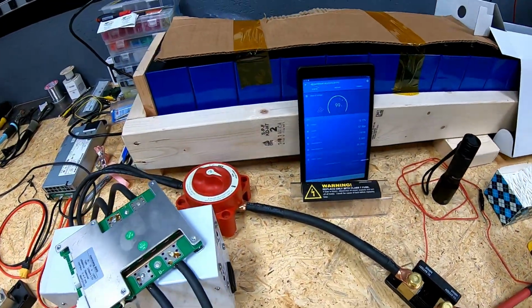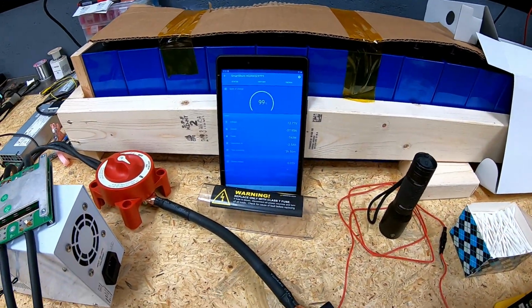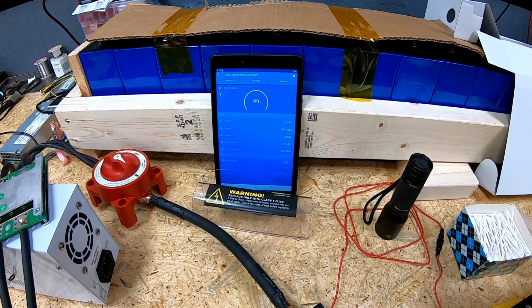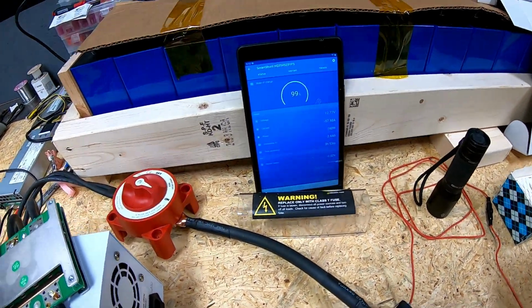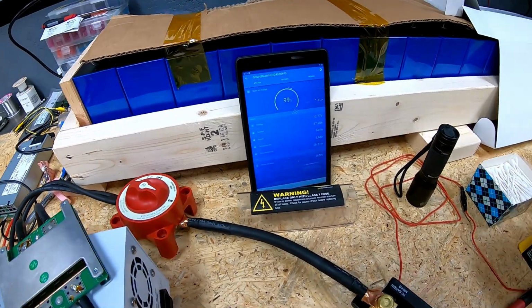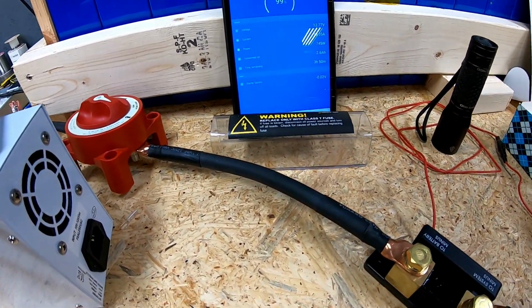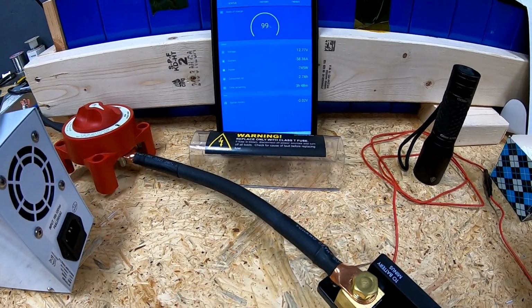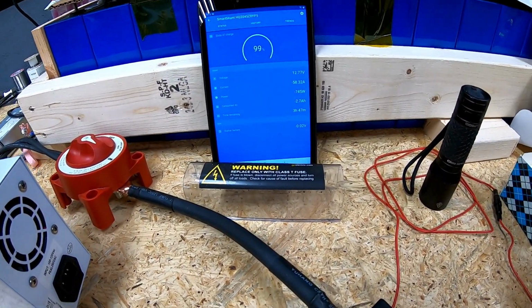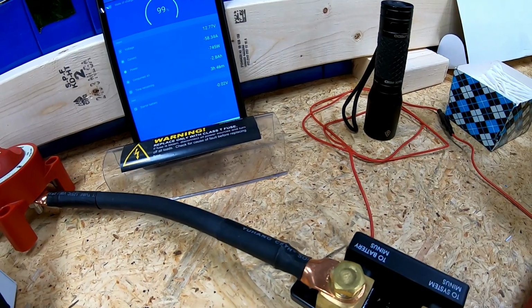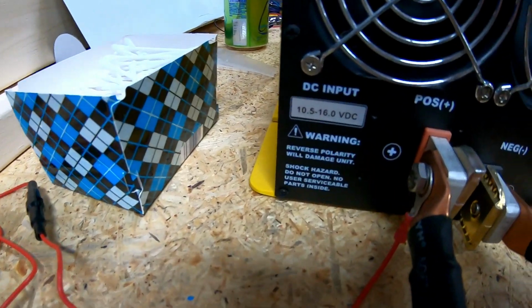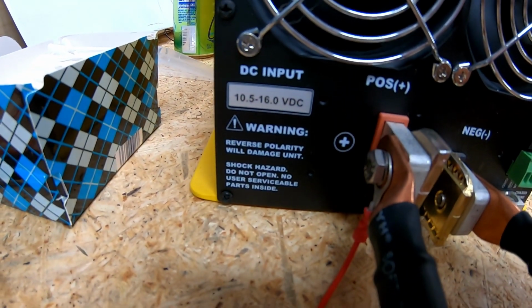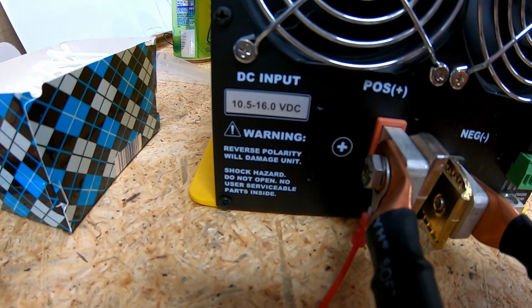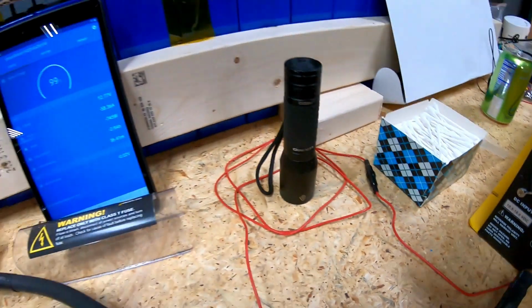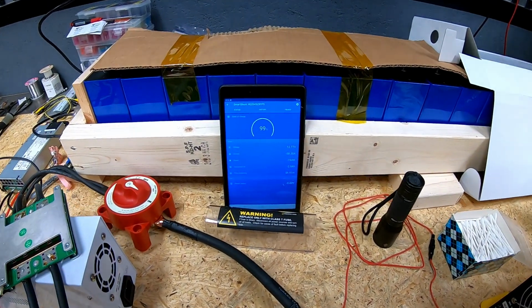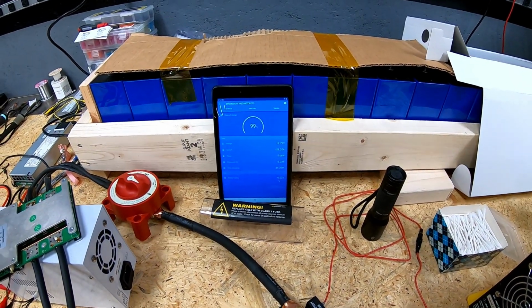We're going to continue to run this and come back periodically to check the status, and see what happens until either the inverter drops out first or the BMS cuts out. Just so you're curious, the inverter is rated for about 10.5 volts, it looks like that will be the cutout. We'll bring you back as the test progresses. Thank you.